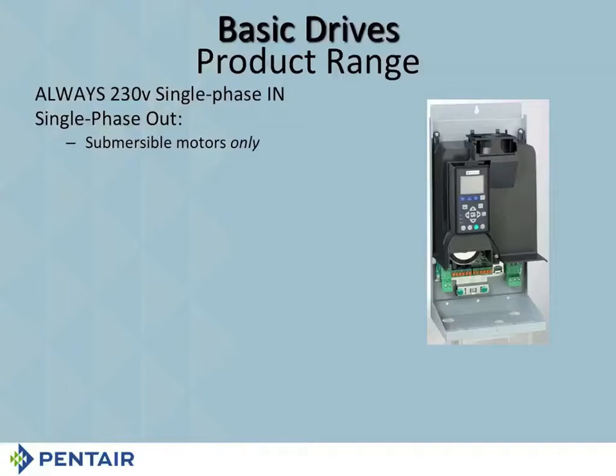They're made differently, and I know that there's 4 different parameters between an above ground motor and a submersible motor. When we first came out with the drive, it was originally designed and intended for submersible motors only. And what wound up happening, some guy insisted, well, it's a drive, it's 3-phase. What difference does it make? A 3-phase motor is a 3-phase motor. He burned up 4 3-phase motors above ground before he realized there was a difference between submersibles and above ground. So just make sure that you understand that, okay? 60 hertz only when you're doing single phase output.